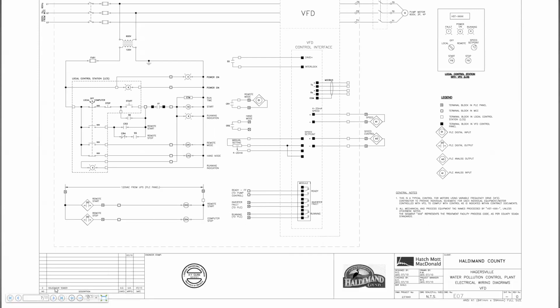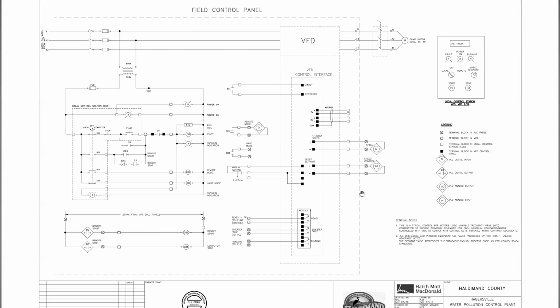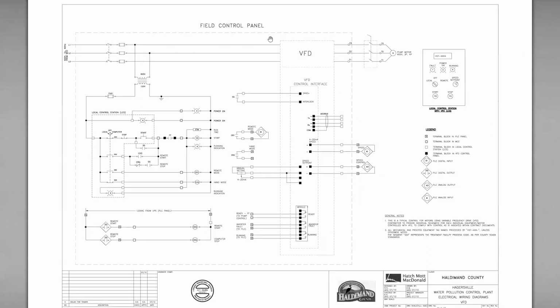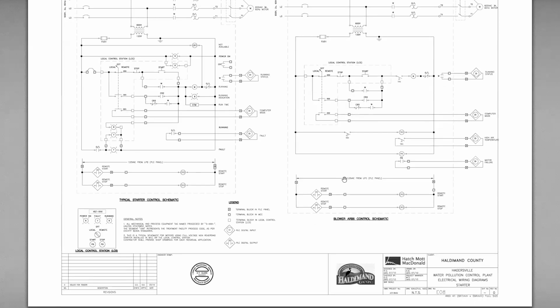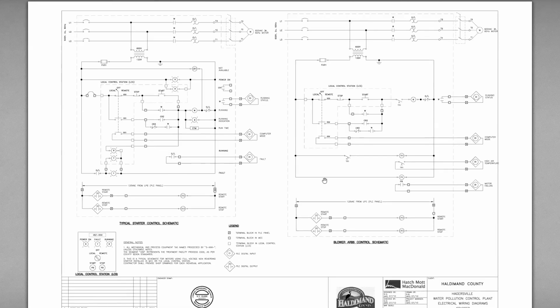All they're doing is, this is for tender, this is conceptual: we need a pump with a variable speed drive that has local control and VFD and PLC control. So this is as detailed as some engineers will get for control systems.